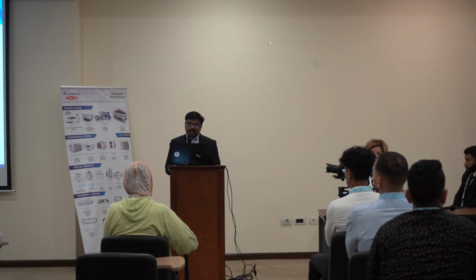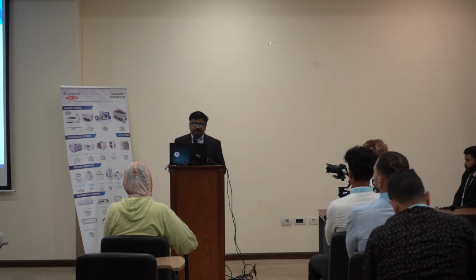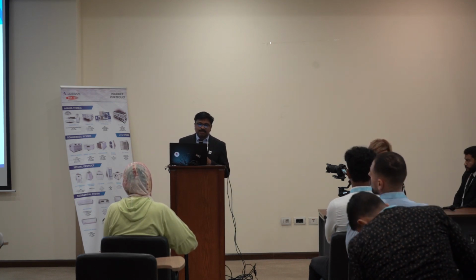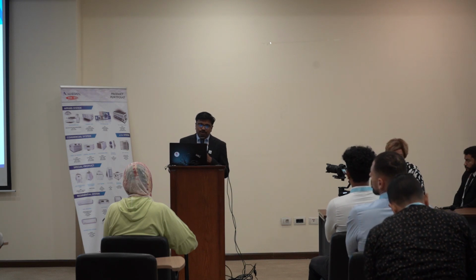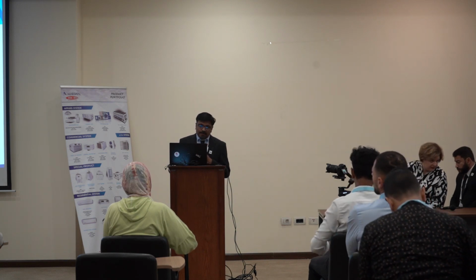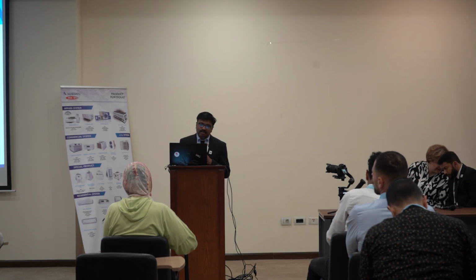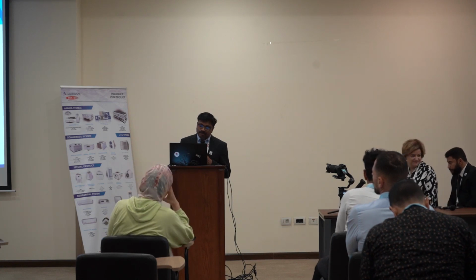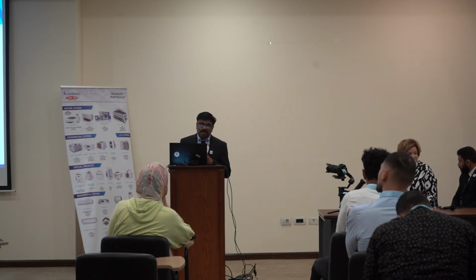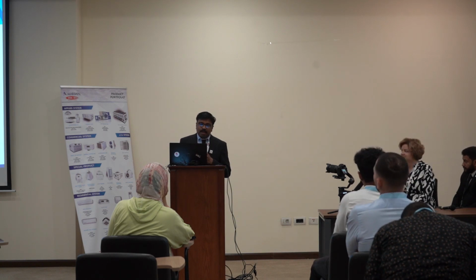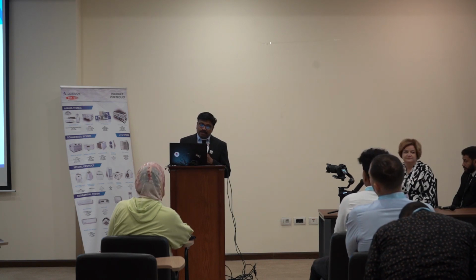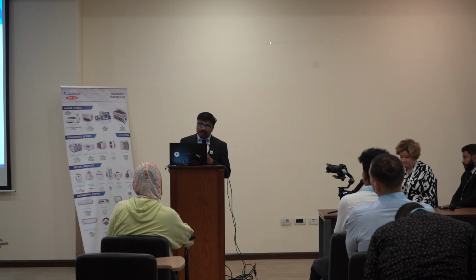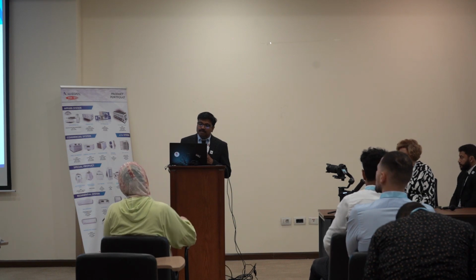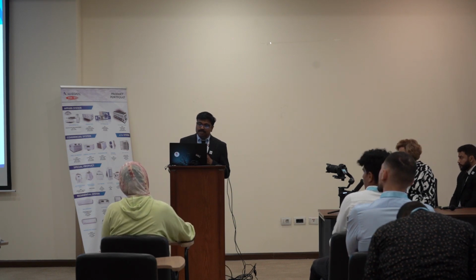And the other feature is the piping flexibility. When we take the distance between indoor and outdoor, when the ODU is above, it is 100 meter, and the largest level, when the ODU is down, this is 110 meter. And the largest level difference between the indoors is 40 meter, and pipe length can be maximum 200 meter between the farthest IDU and the first ODU branch joint.